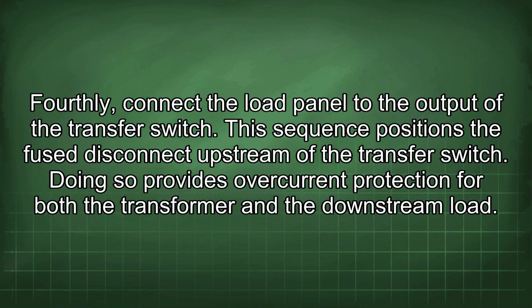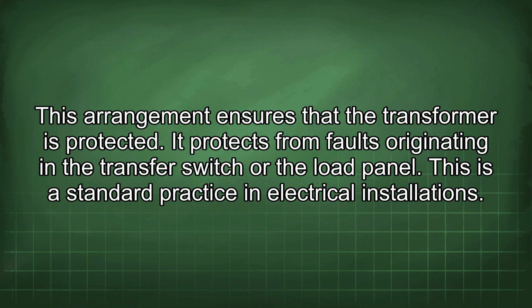This sequence positions the fuse disconnect upstream of the transfer switch. Doing so provides overcurrent protection for both the transformer and the downstream load. This arrangement ensures that the transformer is protected. It protects from faults originating in the transfer switch or the load panel.